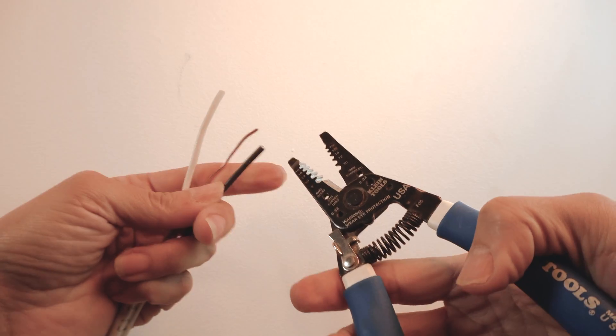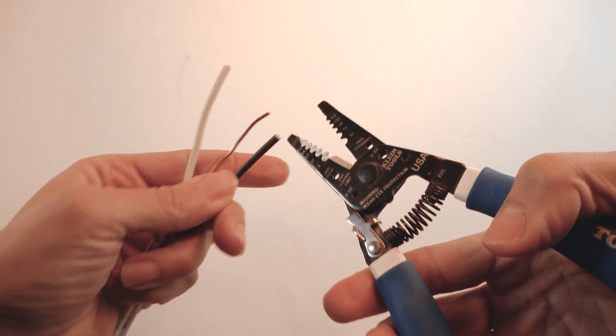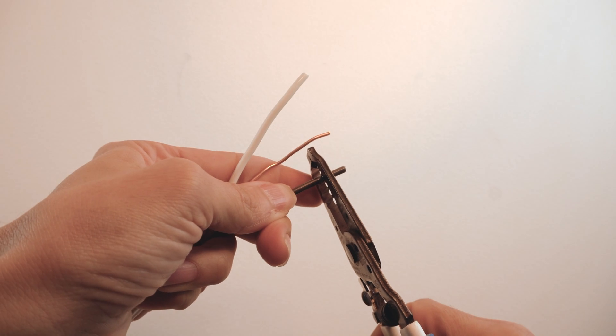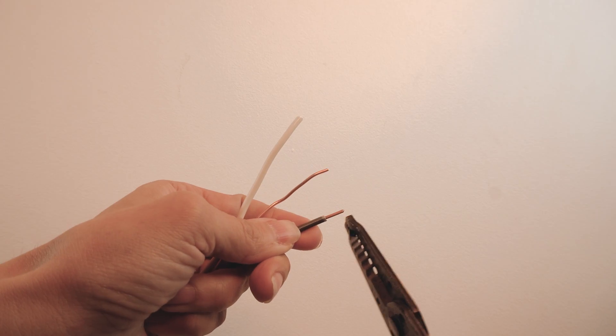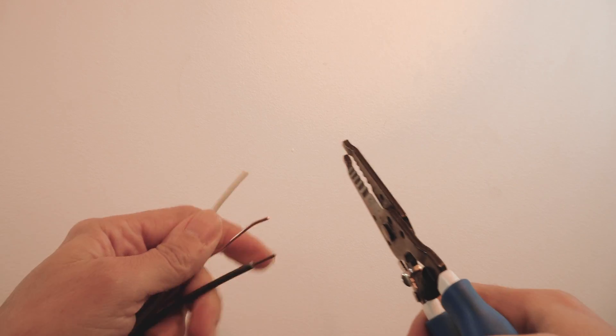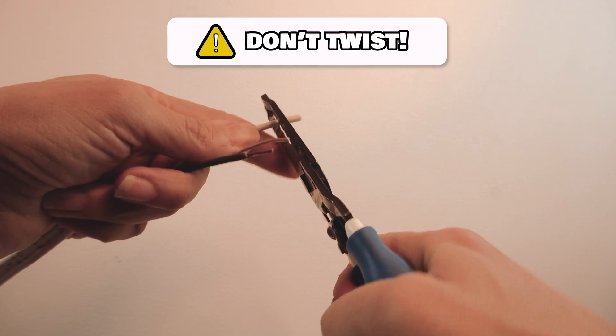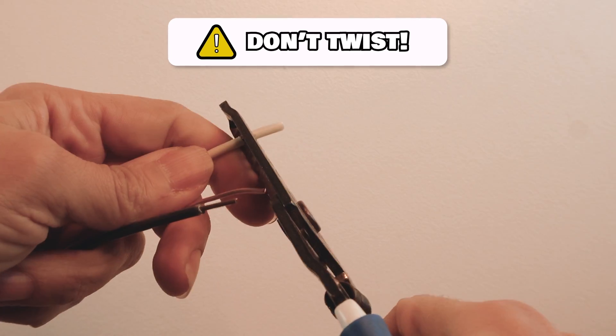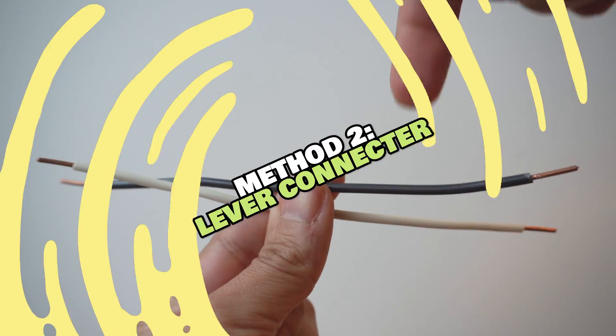Here's how to make a pigtail. You're going to take your wire cutters. I have 14 gauge wire, so I'm going to put it in the 14, like so, and press down. Now, you do not want to yard on that or twist. It's a simple pull away. See that? The sheathing shot off five feet down the road. That's what you want. Now, what you don't want to do, sometimes people do this. They go like this. Don't do that. That's not good. We're just going to do a simple cut and pull it away. That is how you make a pigtail.